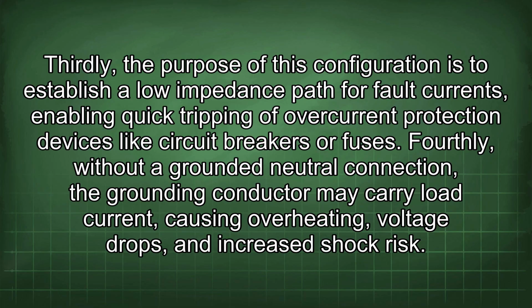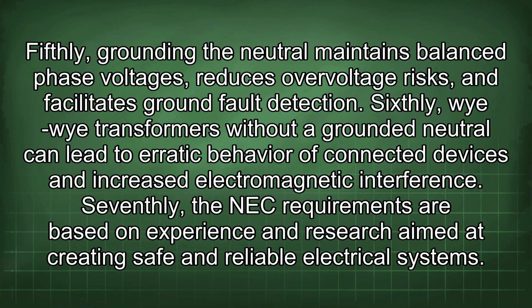Thirdly, the purpose of this configuration is to establish a low impedance path for fault currents, enabling quick tripping of overcurrent protection devices like circuit breakers or fuses. Fourthly, without a grounded neutral connection, the grounding conductor may carry load current, causing overheating, voltage drops, and increased shock risk. Fifthly, grounding the neutral maintains balanced phase voltages, reduces overvoltage risks, and facilitates ground fault detection. Sixthly, Wye-Wye transformers without a grounded neutral can lead to erratic behavior of connected devices and increased electromagnetic interference.